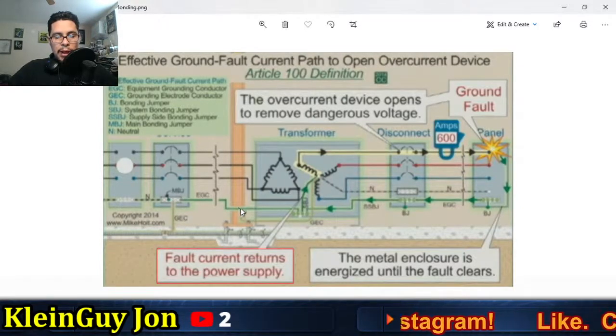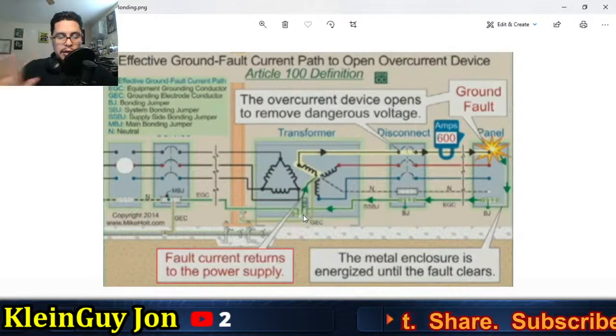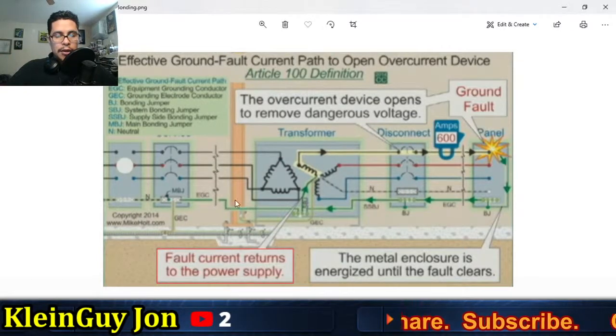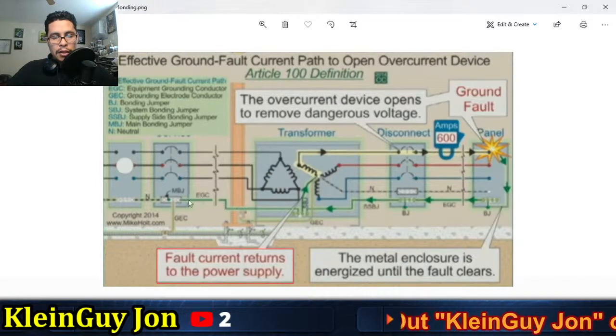I'm going to go back a second. Let's say the grounding electrode conductor is not bonded to the XO, and not bonded from the XO to the metal steel structure. I'm going to take a step back because I kind of rushed that. Electrons are not going through all the building. What's going to happen is it's going to go through here. It's going to go through the metal, all around the metal framing. It's going to follow the ground, and what's it going to think? It's going to think it's going back to this.